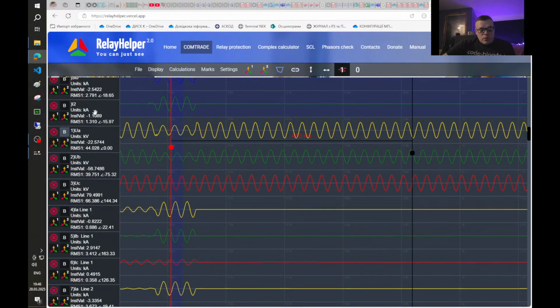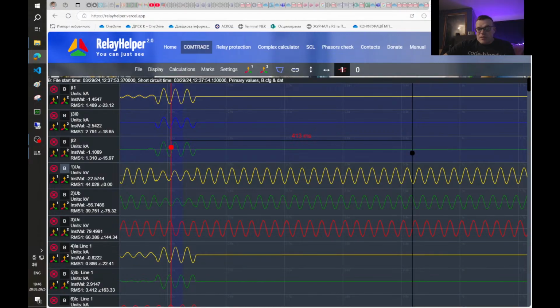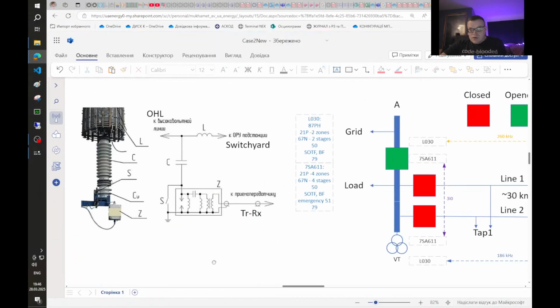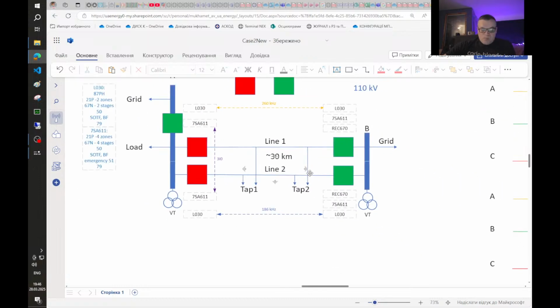So I believe we finished with the substation B side. To make a summary: the second line tripped by phase differential protection, distance protection in 7SA611, and by the first zone of distance protection of L030. On the first line, distance protection also worked, also the first zones of distance protection in Siemens and Hartron devices.